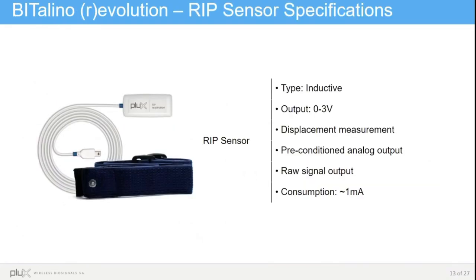Here we show some more technical information about the sensor, which is inductive, has an output limited between 0 and 3 volts, where the baseline is around 1.5 volts. It measures the displacement and not the position, as mentioned before, and allows the acquisition of raw signals, with a low consumption of around 1 milliampere.